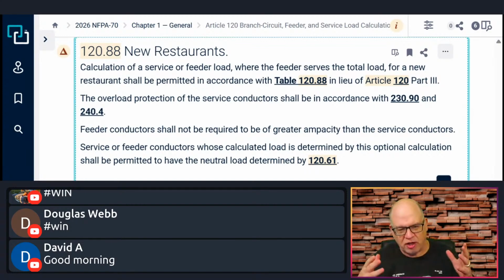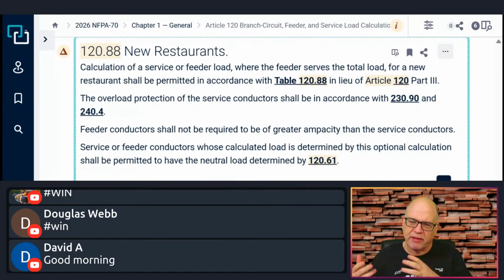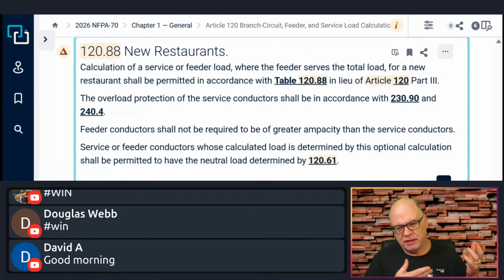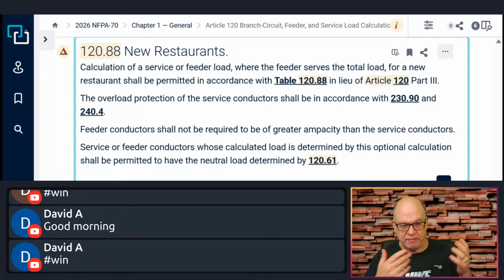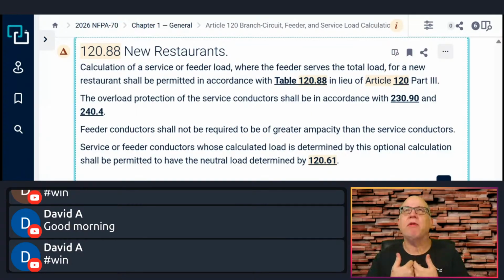If we size the load and we size the service conductors for that load, then there's no need for that feeder to be larger than the service conductors, right? Makes sense, right? I mean, equal to size. There would be no need for me to have service size conductors of one size and then have feeders that are larger. It wouldn't make sense to do that, okay?